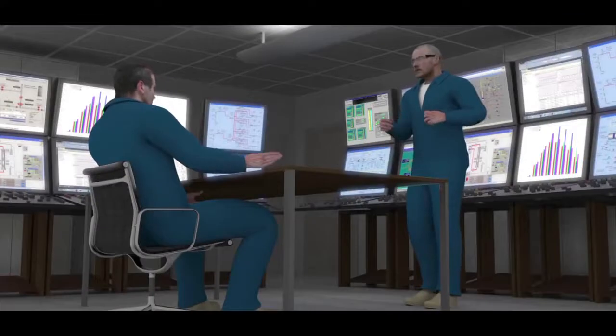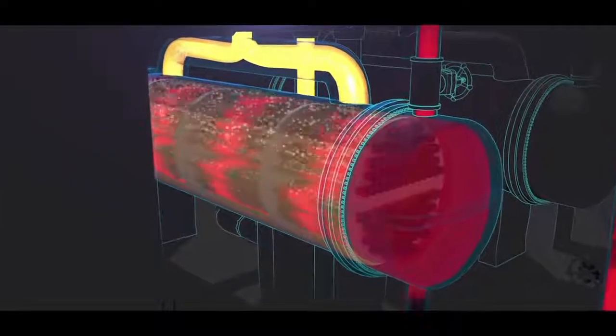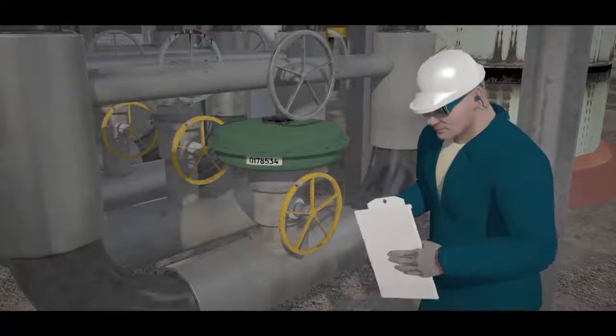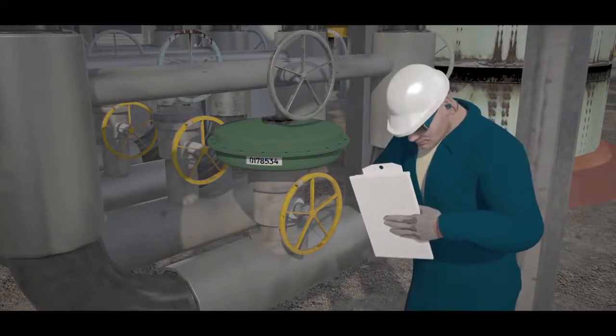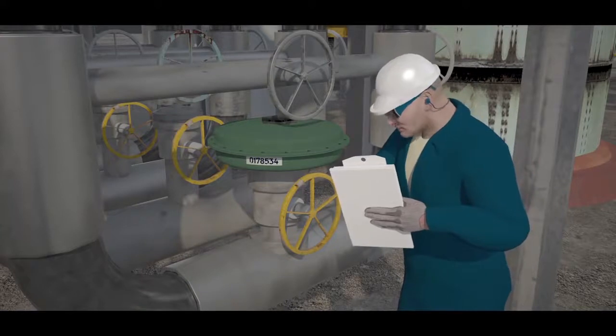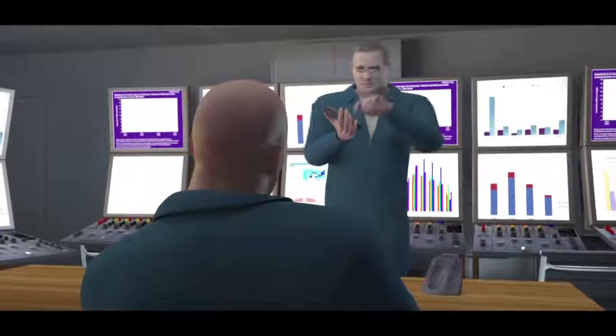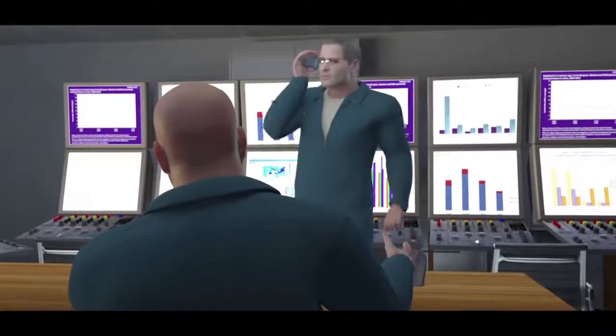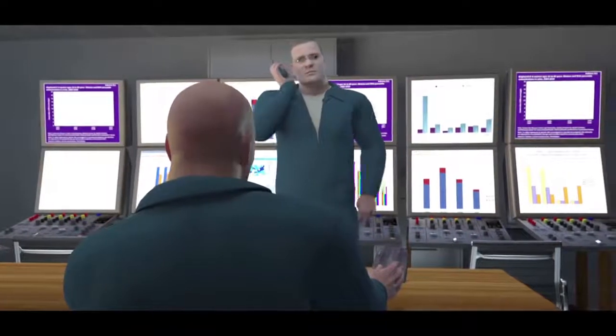On June 13, 2013, during a daily meeting with operations and maintenance personnel, the Williams plant manager noticed that the water flow rate through the operating reboiler had dropped gradually over the past day. The operations supervisor informed the group he would try to identify the problem. He went into the plant to evaluate the water flow rates. The operations supervisor informed several personnel that fouling within the operating reboiler could be the problem, and they might need to switch the reboilers. He attempted to meet with his manager so they could get the necessary maintenance and operations personnel involved, but his manager was not available.